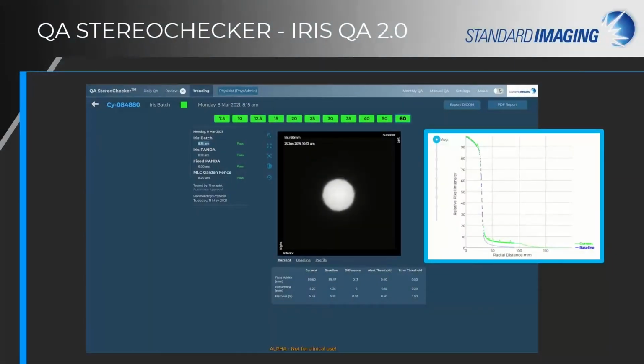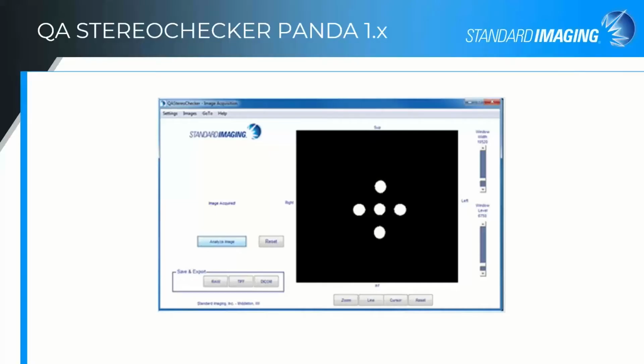From a basic software interface to a richly enhanced user interface, QA StereoChecker continues to provide amazing 200 micron resolution, detecting errors well below Accuray's recommended thresholds for all tests. The ability to examine radial profile results against a baseline at every 5 degrees provides the details behind the results to facilitate troubleshooting should any issues arise in the iris batch test.